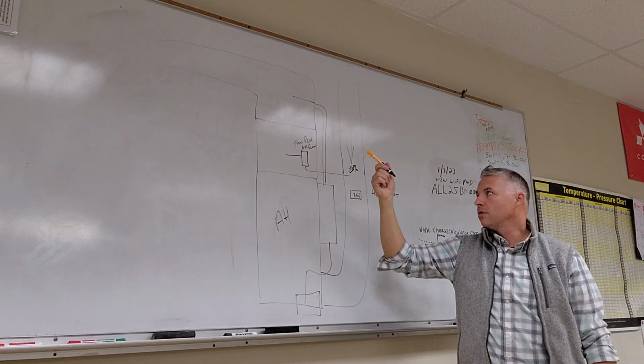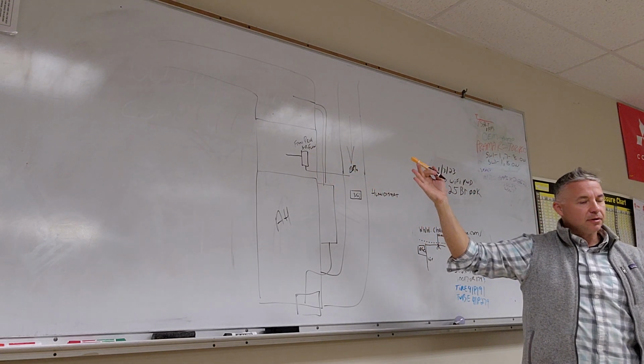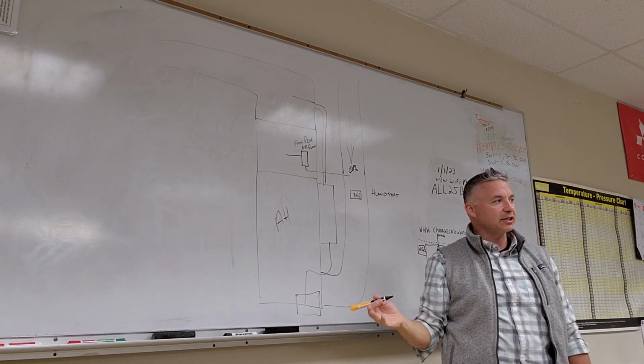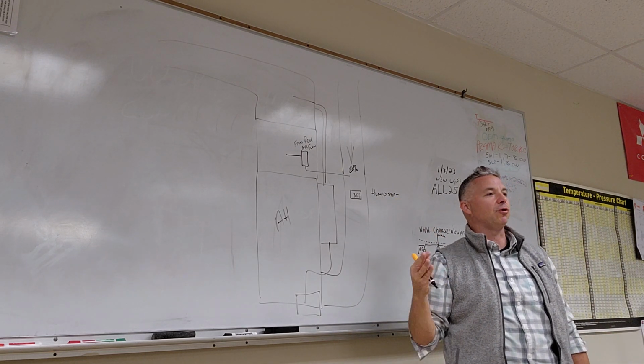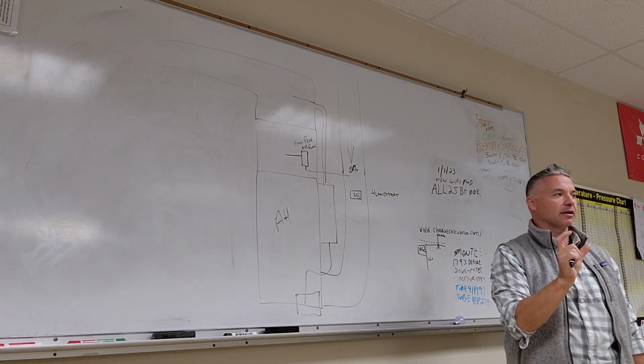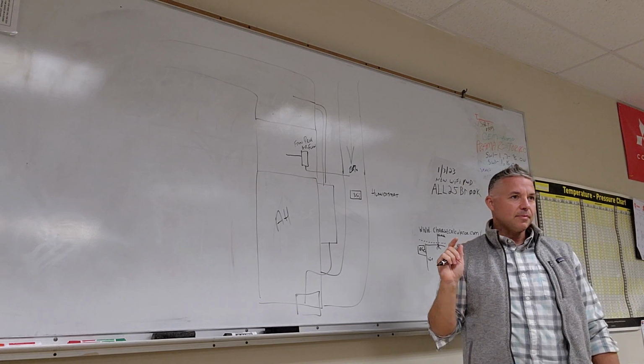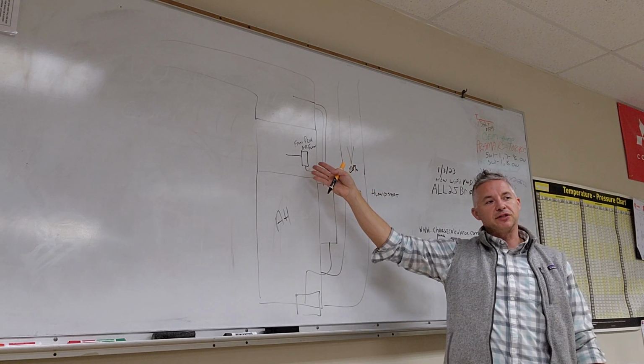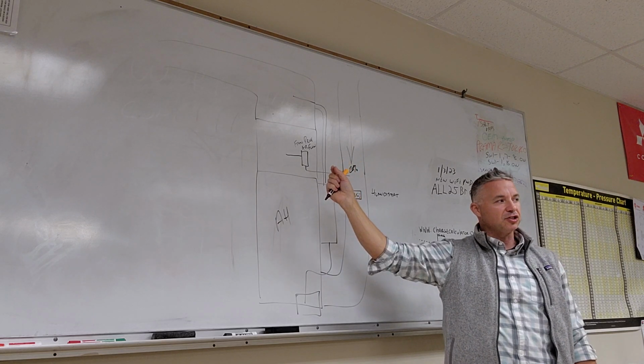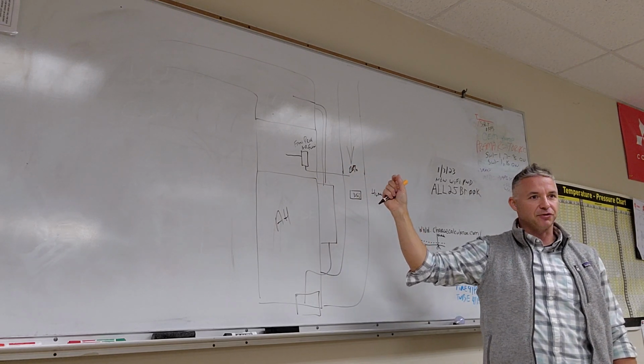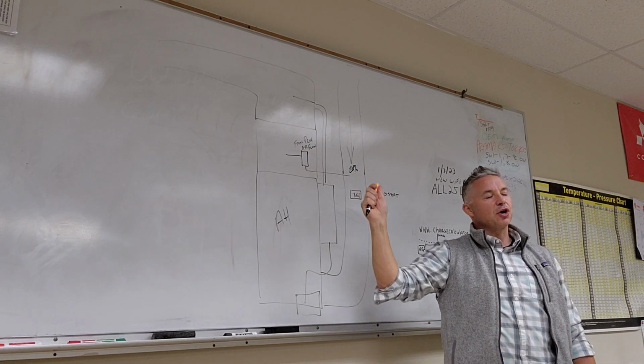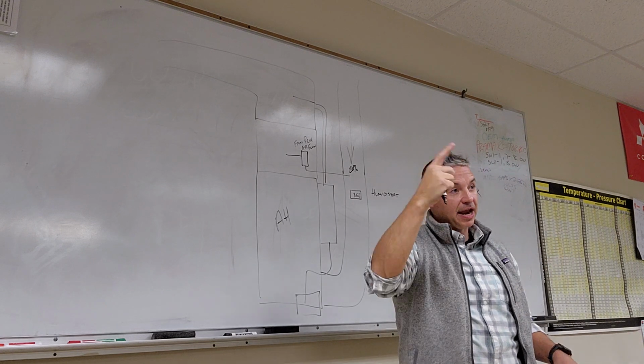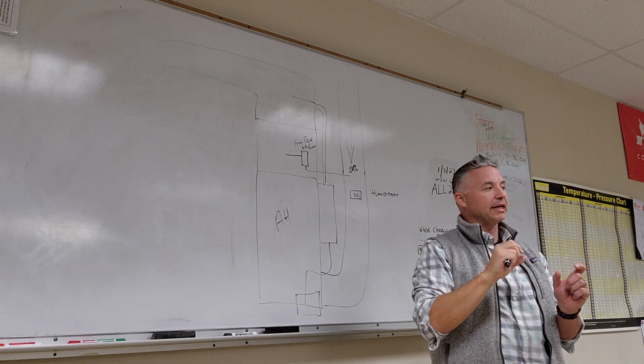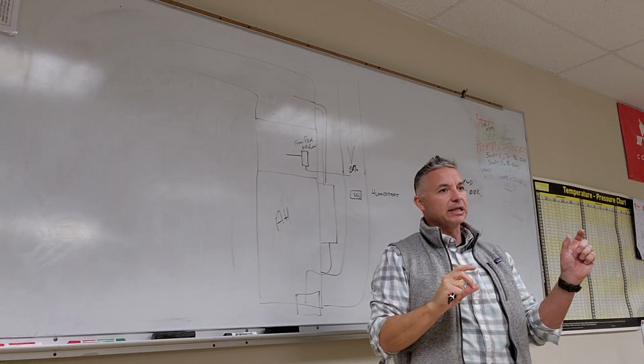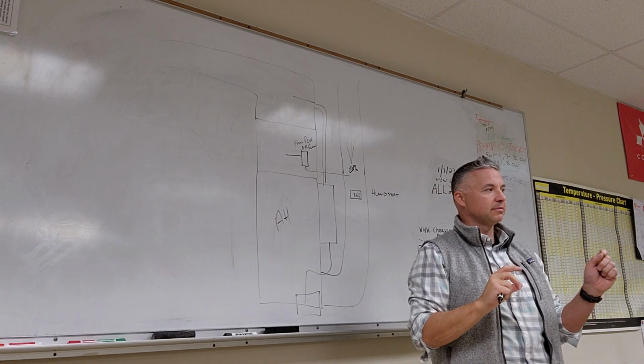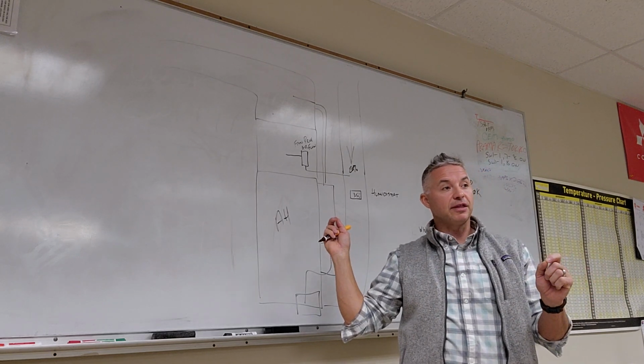And we're using an airflow or fan proving or pressure switch as opposed to a current sensing relay. A current sensing relay can do the same thing for us, but it's a less reliable switch. It's a less reliable electronic thing. So an air proving or fan proving switch is more reliable. It's typically adjustable, so you can set it to what your fan speed is. You can have it match your fan speed. And sometimes a current sensing relay, especially with ECM motors, the fan will ramp all the way down. Sometimes, because you don't get that hard shutoff on the fan, that electronic relay inside that current sensing relay will stay pulled in. So there's potential there for it to leave that humidifier running.